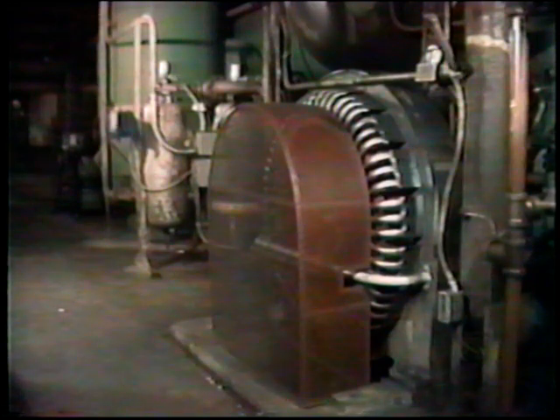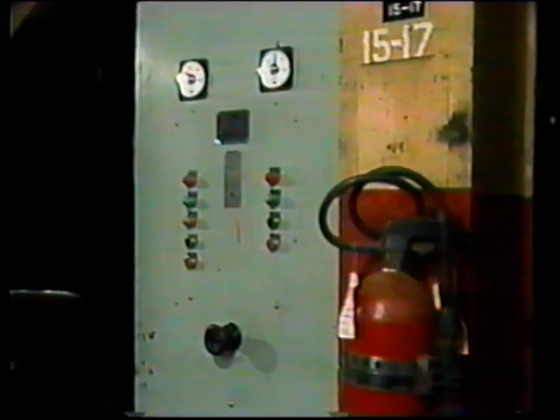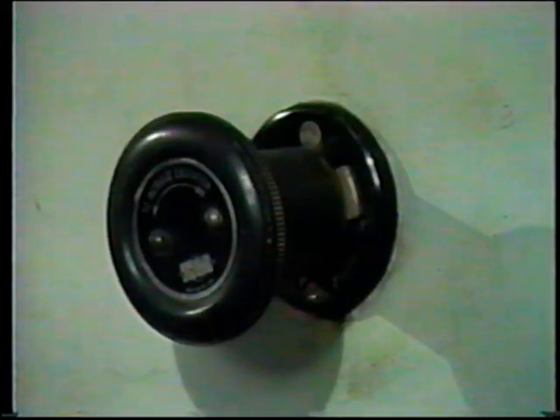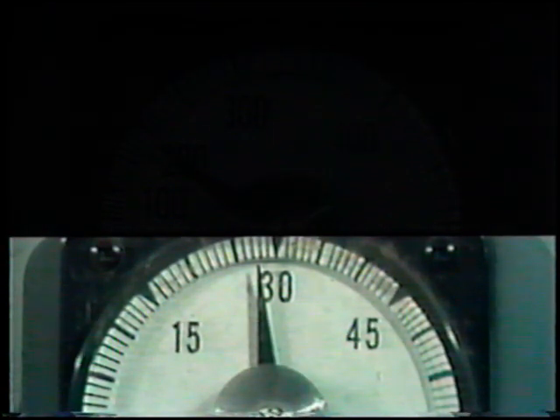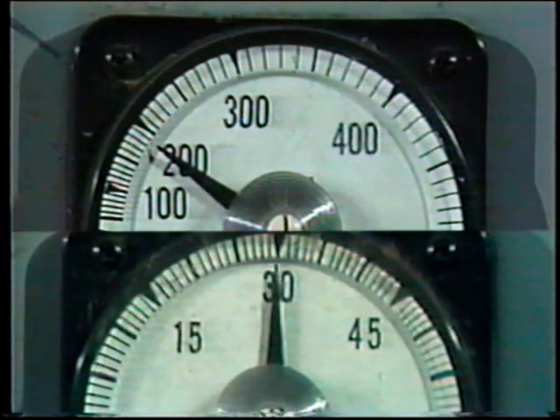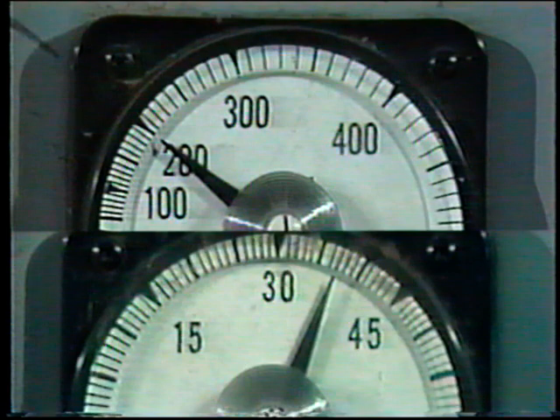We'll use a synchronous motor that is operating at unity power factor. It's operating at maximum efficiency. Direct current is supplied to the rotor windings of the synchronous motor through this controller. We're going to use this rheostat to control the current going through the rotor windings. We'll be able to read the amount of current the rotor is using on this meter. The amount of three-phase current flowing through the motor stator is indicated on this meter. Watch the top meter closely. When we raise the current flow in the rotor, the AC meter shows an increase in stator current flow. That means the motor's operating less efficiently.